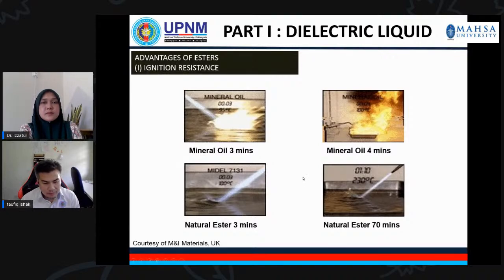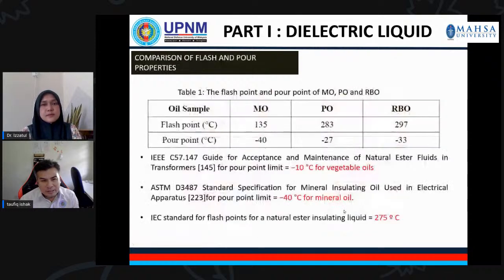So next, we look at ignition resistance: how good that particular oil is at resisting ignition. The next one is the flash point and pour point properties of the oils. For this case, I did a study for palm oil and also rice bran oil. The flash point for mineral oil is around 100 degrees C, lower than palm oil and rice bran oil, which is more than 250 degrees C. The good thing about a high flash point is that for vegetable oil, you require very high temperatures to make the oil flash and cause a fire.